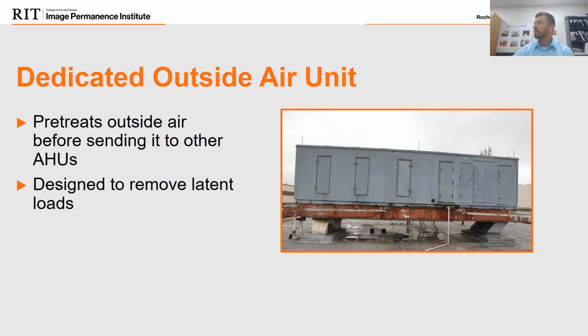Chris, can you recommend any other ways to reduce energy consumption in tropical climates? One of this type of unit, the dedicated outside air unit, would be a good way, but I hate saying it, it's a case by case scenario, because it depends on the facility and the conditions they're trying to achieve. But we actually worked with a couple institutions in Louisiana and I believe Florida that had a dedicated outside air unit, and that was their main method for breaking that high heat, high moisture content that was coming in, to really get that condition and then send it to the other units.